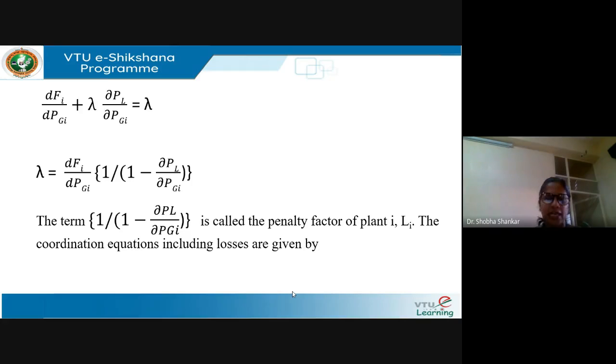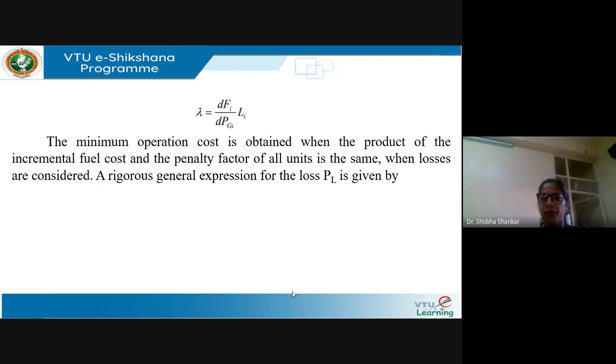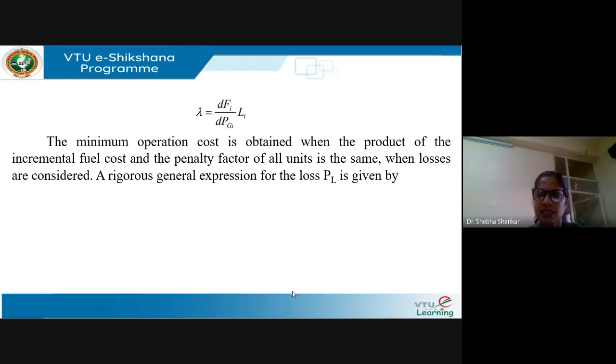Lambda can be expressed as dFi/dPGi multiplied by 1/(1 minus partial PL/partial PGi), where the term 1/(1 minus partial PL/partial PGi) is called the penalty factor of plant i, denoted Li. The coordination equation with losses is therefore: lambda equals dFi/dPGi times Li. When transmission losses are neglected, partial PL/partial PGi equals 0, so Li equals 1, and lambda equals dFi/dPGi. The minimum operation cost is obtained when the product of incremental fuel cost and penalty factor of all units is the same.